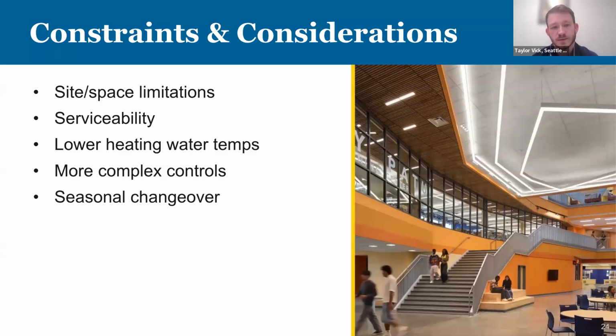Around serviceability as well, you generally need to access all 4 or 5 sides of the equipment, so it's important to have space available. That's one of the benefits of a centralized system—instead of working in a closet with a heat pump up against a wall, we have a lot more space in these plants to work with the equipment. It's really nice to have that.